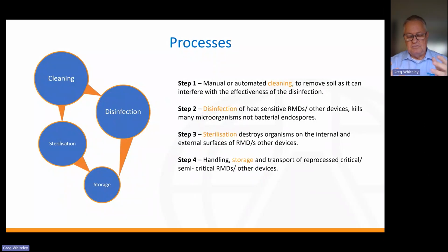a sterilisation process and you're going through autoclaving, that is a heat and moisture sterilisation, you're probably using wrapping, and those wraps have got a whole pile of other material. Again, we can't cover everything today, but they're going to be wrapped, and there will be limits on how those devices can be stored. For unwrapped devices, the sterilisation or disinfection needs to be done as close as possible to the point of clinical use, so that they can be immediately used and then reprocessed.